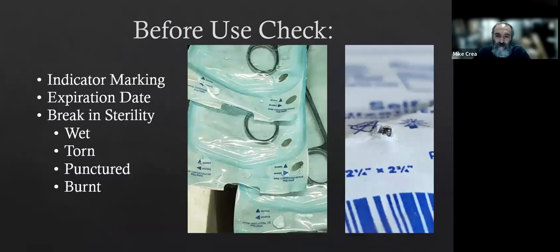So you can see here the package on the left, it did turn brown like it was supposed to. However, when the person pulled them out, you can see there's still watermarks on there. If it's wet, that's considered a break in sterility, and the packages actually are not sterile if they come out of the autoclave wet. If they're torn, if they're punctured, if they're burnt, those are all considered breaks in sterility. We would have to open up, reprocess, and repackage and re-sterilize everything before we can use it.